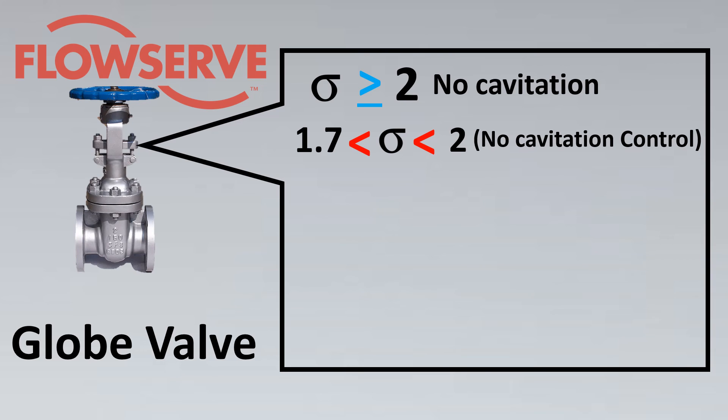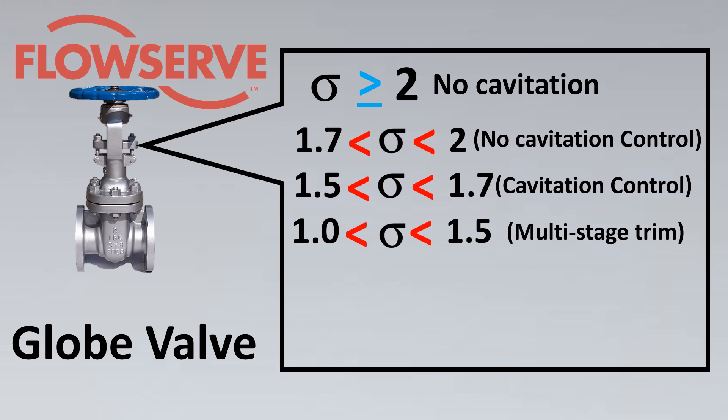If your cavitation index is between 1.7 to 2, there is no special cavitation control that the vendor recommends - this is like our incipient cavitation. But when the value is between 1.7 to 1.5, some cavitation control would be required, like having a hardened trim material could be sufficient. When you're getting to the range between 1 to 1.5, you might require a multi-stage trim. This is something serious - there are chances of very severe cavitation happening here. And finally, if it goes below one, then flashing is occurring.